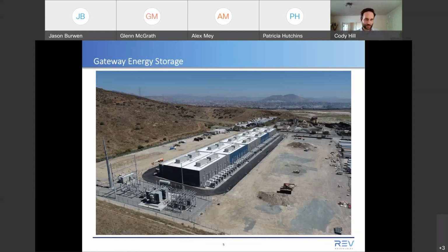This facility you can see here is the Gateway Energy Storage Facility. It's a 250 megawatt lithium-ion battery. When we initially energized it last summer, it was the largest project in the world. It has since lost that crown and then regained it due to some maintenance issues at the world's largest facility. We've expanded it since then, so we've now got 700 megawatt hours of operational batteries installed inside these warehouse-style buildings. What you're looking at: substation in the front, where the AC power comes in off the transmission grid, gets converted to medium voltage, 34.5 kV in this case, and that gets distributed underground to all these little boxes alongside this long 70,000 square foot building.